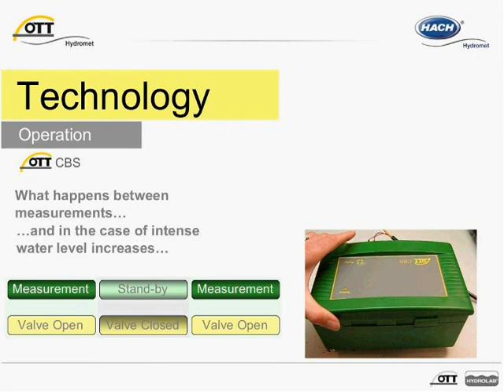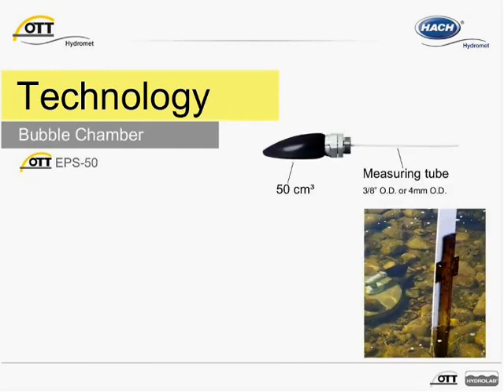The CBS acts quickly to drastic water level changes without lag. For example, if the water level increases by 10 feet within a measurement interval — which is a real rapid rise — the CBS will recognize the change in pressure within 14 seconds of initiating that measurement. This holds true in water depths up to 16 feet. If water depth is greater than 16 feet, up to say 50 feet, the unit will recognize a water level change of 3.3 feet within the measuring interval of one minute.